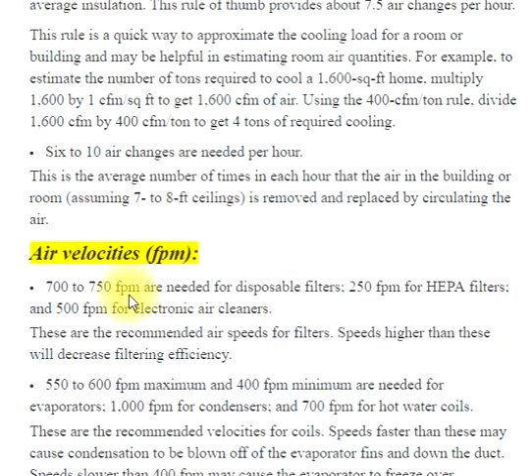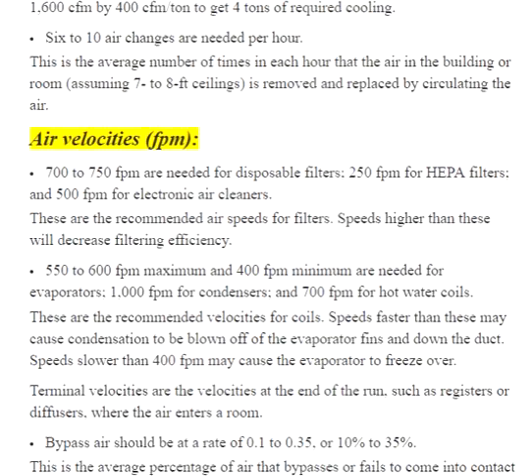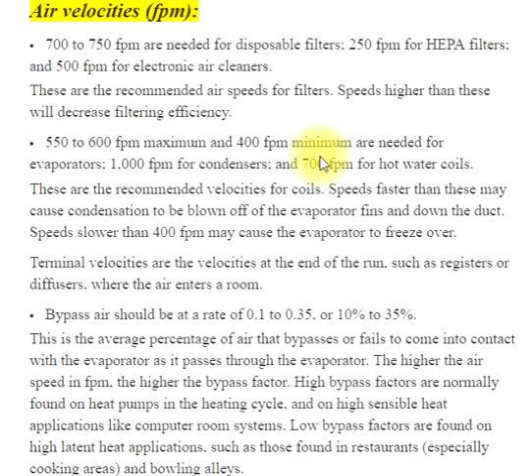Air velocities in FPM: 700 to 750 FPM are needed for disposable filters, 250 FPM for HEPA filters, and 500 FPM for electronic air cleaners. These are the recommended air speeds for filters. Speeds higher than these will decrease filtering efficiency.